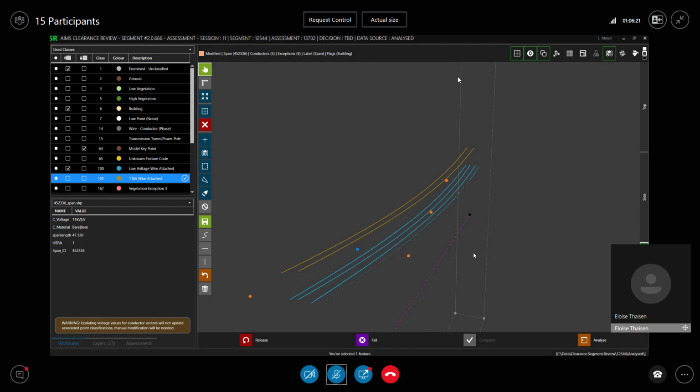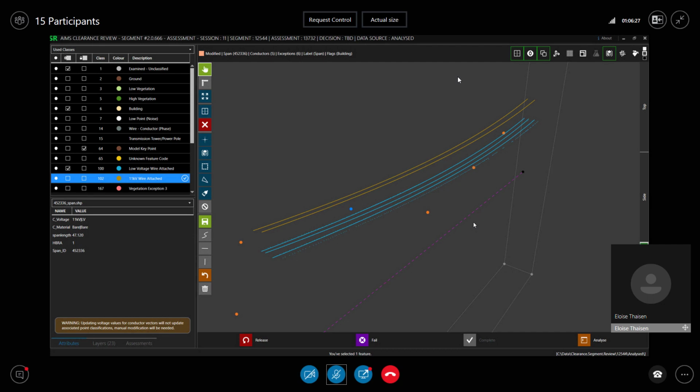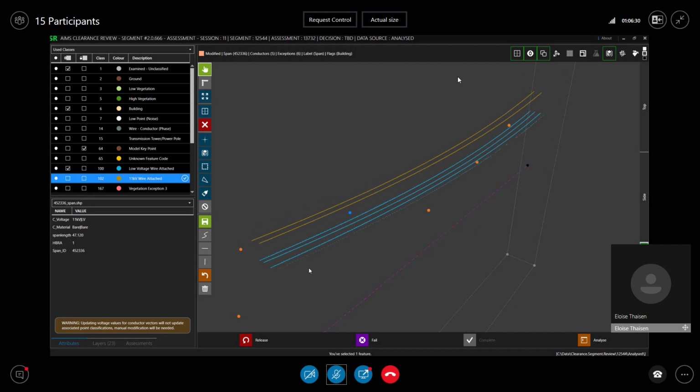With the conductors that are present for the 11 kV, we can't turn them off while we're doing this. They will remain, but you can turn all of them off and you can just view your LiDAR points. So you can do that if it's easier for your field of view, but if you wanted to know which conductors already have this catenary vector made, you can turn it back on. So to make a catenary, the system actually only requires a small amount of points. It only requires 3 LiDAR points to actually make these 3D vector conductors.